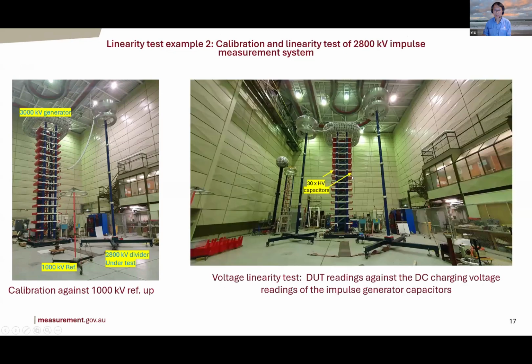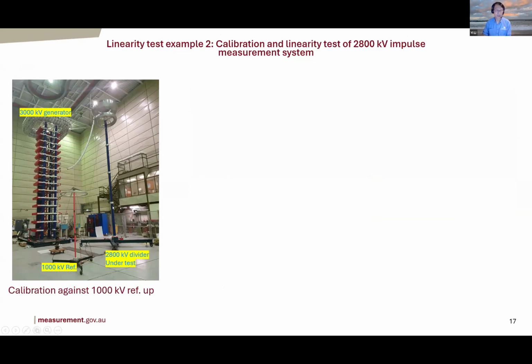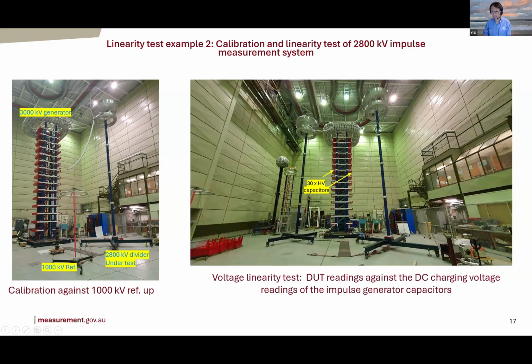This is another example. So this 2,800 kV impulse divider, which is a capacitor divider, needs to be calibrated. The reference only goes up to 1,000 kV. So you measure the reading or ratio of that up to 1,000 kV. Then you do the linearity test. In this particular case, the linearity test is done by comparing the reading from this measurement device with the reading of the charging voltage of this generator's capacitors. So these are the capacitors for charging the impulse generator. You charge them in parallel, you switch them into series to generate the high voltage pulse. But the reading of that charging capacitor voltage, which is DC, can be used as another linearity test reference. Quite often, that works if you do that properly.